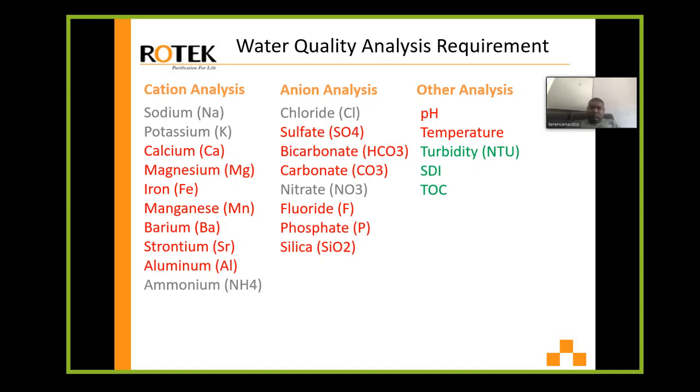A lot of times you see the water is transparent and clean, turbidity is very low, but SDI is that high. That tells you there are a lot of tiny particles that eyes cannot see in the water. The SDI requirement for our feed should be below 3, but now they are getting 5.3.